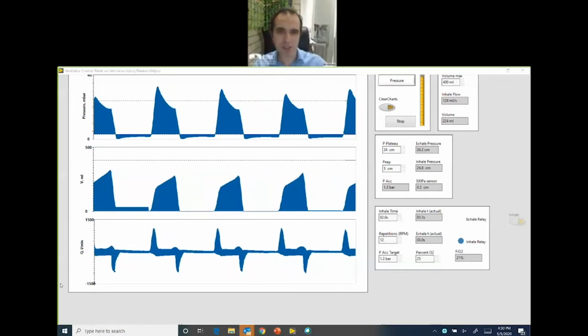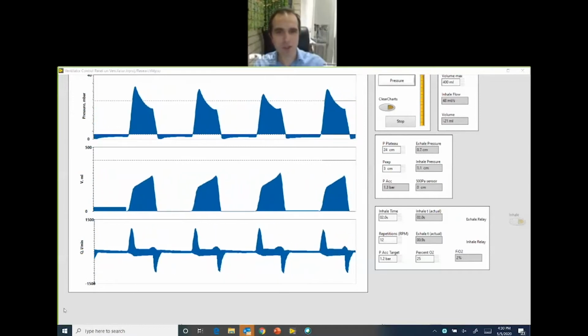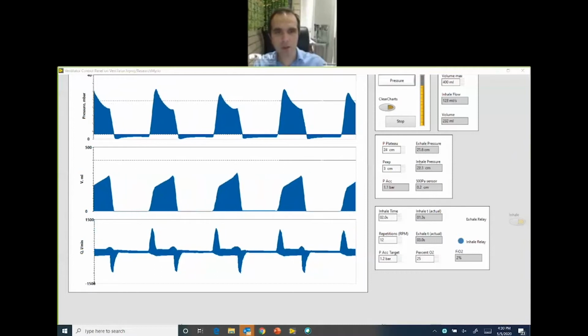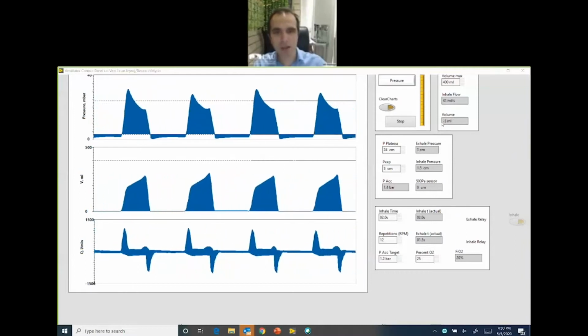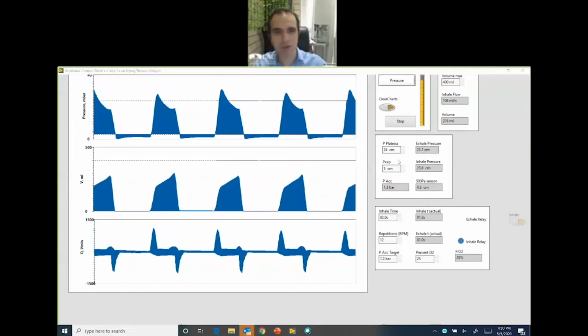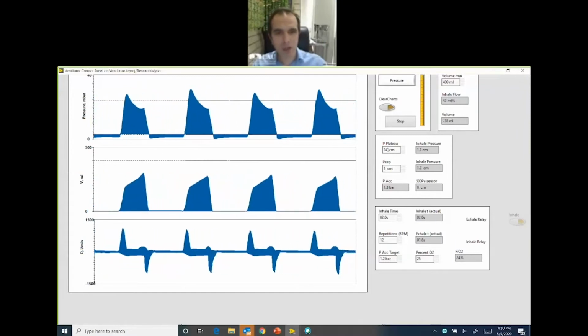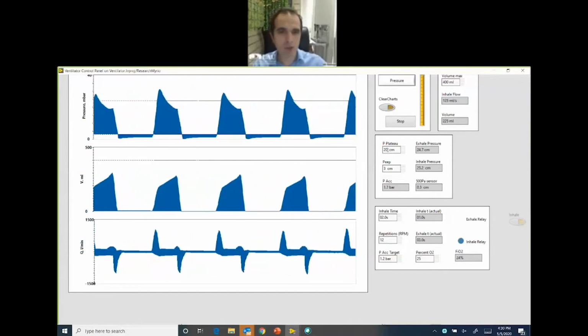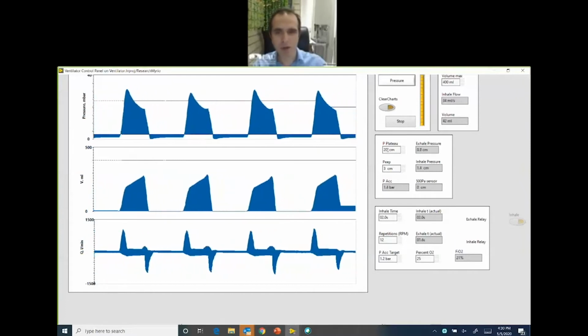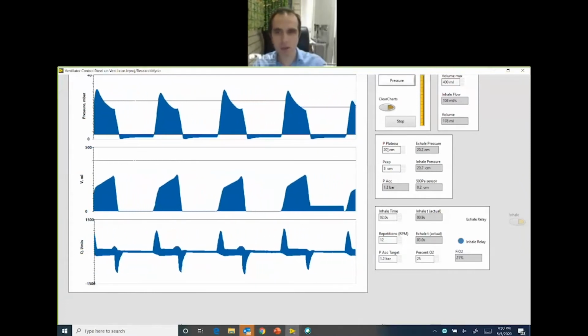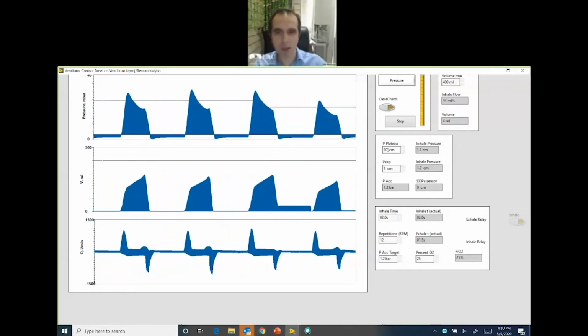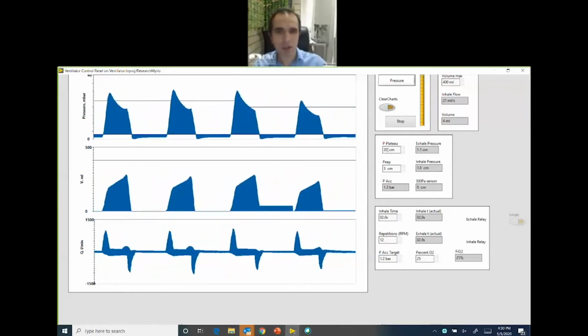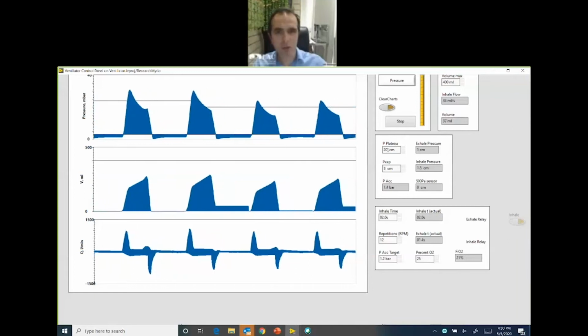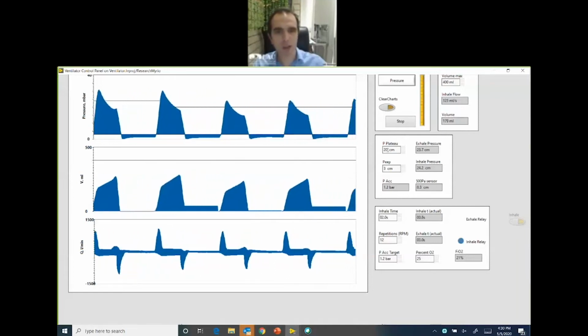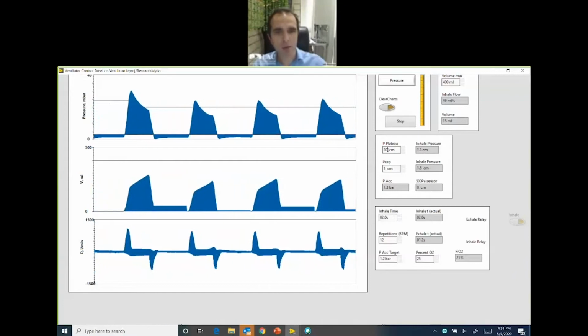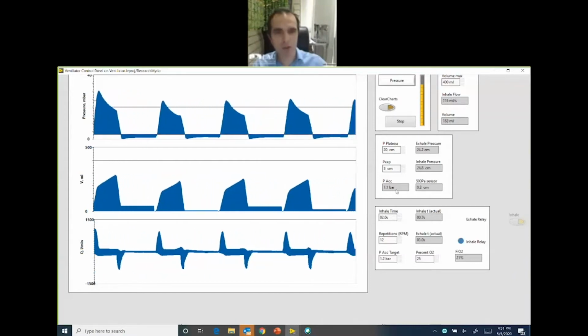To show you what's inside the final design, what is it comprised of? These are the internals of the final product. So we have different components. We have the accumulator, which is used to accumulate the air, the two types of air that Dr. Akle talked about, the air and the oxygen. They will both go through the inlets that you see over here. We have pressure regulators where we control the value of the maximum pressure that can be allowed to go into the regulator. And then we have solenoid valves that control this process.